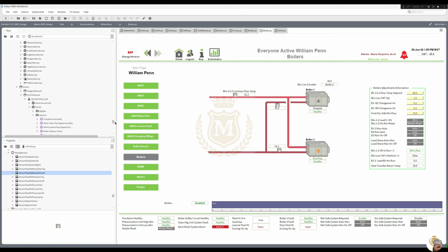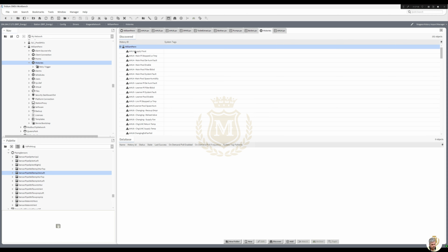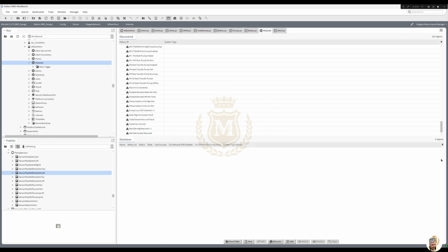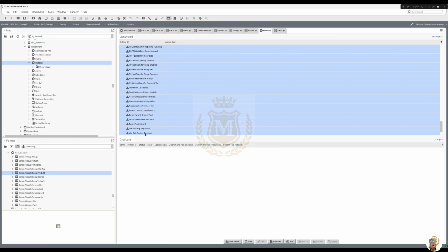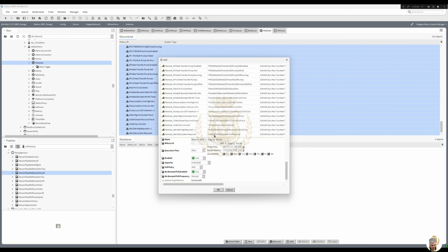So we want to go to, we don't want that anymore now. We want the Niagara. Yeah, they're all my points. Histories. Discover. Take all them. Drop them into the supervisor. Highlight them all. Interval. Every 1 hour. Bring them in. Unlimited.